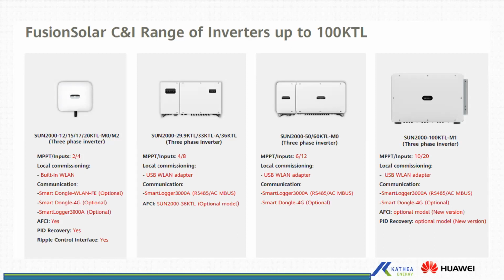A smart dongle 4G performs the same function as the smart logger, but it has more limited functions. It's also responsible for connecting the system to the monitoring portal. But this range is only available for the 12 to 20, 50, 60, and 100. The 29 to 36 KTL currently is not supported. However, on our M1 version, which is scheduled to be coming in second quarter of this year, it will support the smart dongle.